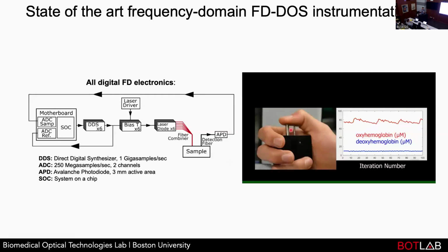And if you're in a layered structure, like the finger, where you have skin that has one scattering value and absorption value, and then maybe subcutaneous fat underneath, and then an artery, you might be measuring different portions of those layers that all have different optical properties. So a perceived change in optical scattering at the surface may not be because the blood is changing its optical properties, but because you're measuring more superficially, and a larger portion of your measurement volume is from skin during systole. During diastole, you're measuring deeper, so your measurement volume includes skin and adipose tissue and so forth. Hopefully that was a reasonable explanation. We call that the partial volume issue.